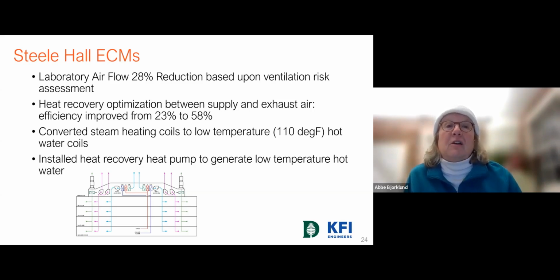We also looked at heat recovery optimization. It had a runaround heat recovery system that we calculated was only 23% efficient. And by redesigning that system, we were able to bring it up to 58%. It's still a runaround system because it's a lab building. We couldn't do an enthalpy wheel safely. We also converted the steam heating coils to low temperature systems, and we installed a heat recovery heat pump to generate that low temperature hot water for providing reheat and heating in the building.